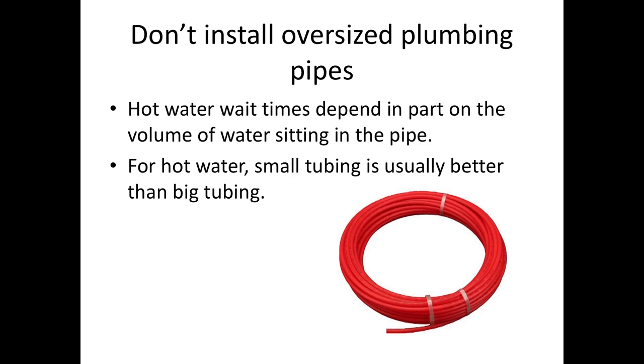Don't install oversized plumbing pipes. This is counterintuitive, but if you're waiting for hot water at a remote faucet, you don't want 3/4 inch copper line. I used to think I wanted a great plumbing system, so instead of running 1/2 inch copper I'd run 3/4. But that means a higher volume of hot water has to run through before the water from the heater gets there. So more people are saying 3/8 inch will work. Whether you can use that for an individual application depends on your local plumbing code, but believe it or not, small diameter tubing makes sense for remote hot water faucets.